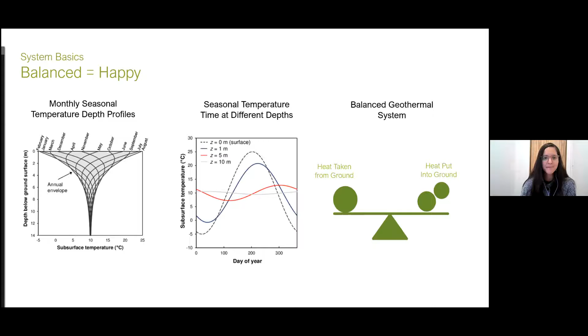The failure of the system wouldn't be instant, but it is something that can creep up over time if left unattended, if the system either isn't monitored or balanced in design. And the failure, what happens is that the temperature shift within the ground just goes beyond what the workable temperatures of the heat exchangers are. And obviously this is something that we want to avoid, as retrofitting a building with a conventional system after a geothermal ground loop failure is extremely costly and disruptive, and not something we want to do. So constant monitoring of the system is important.